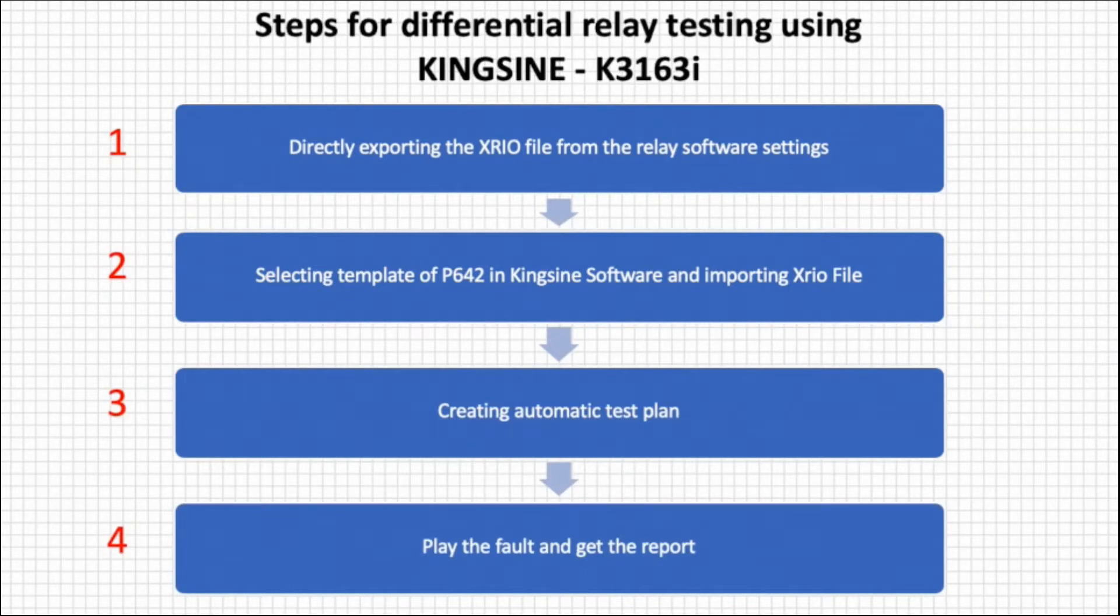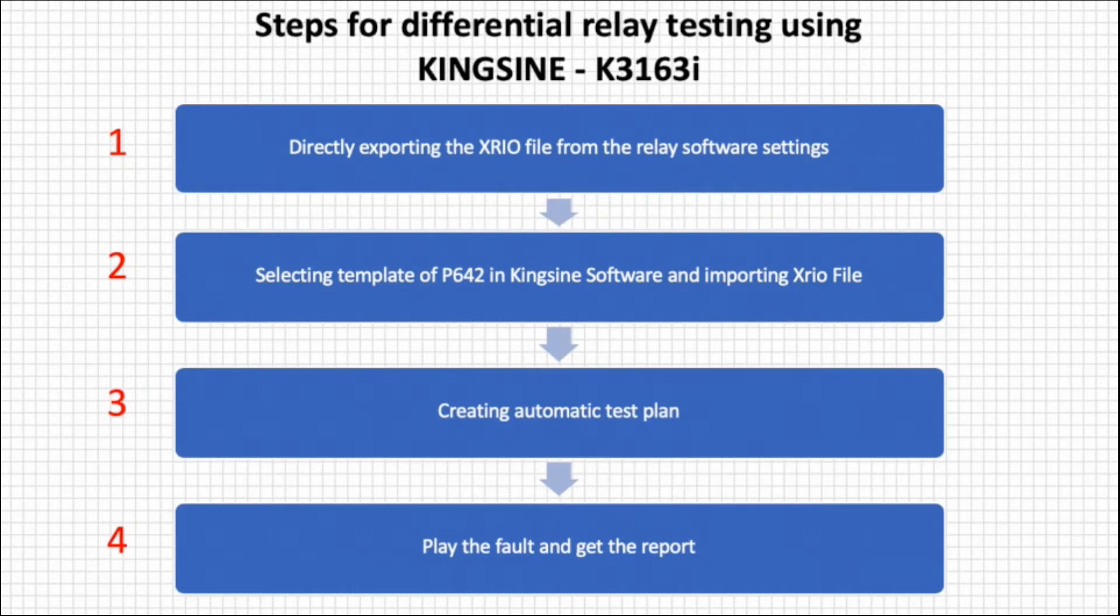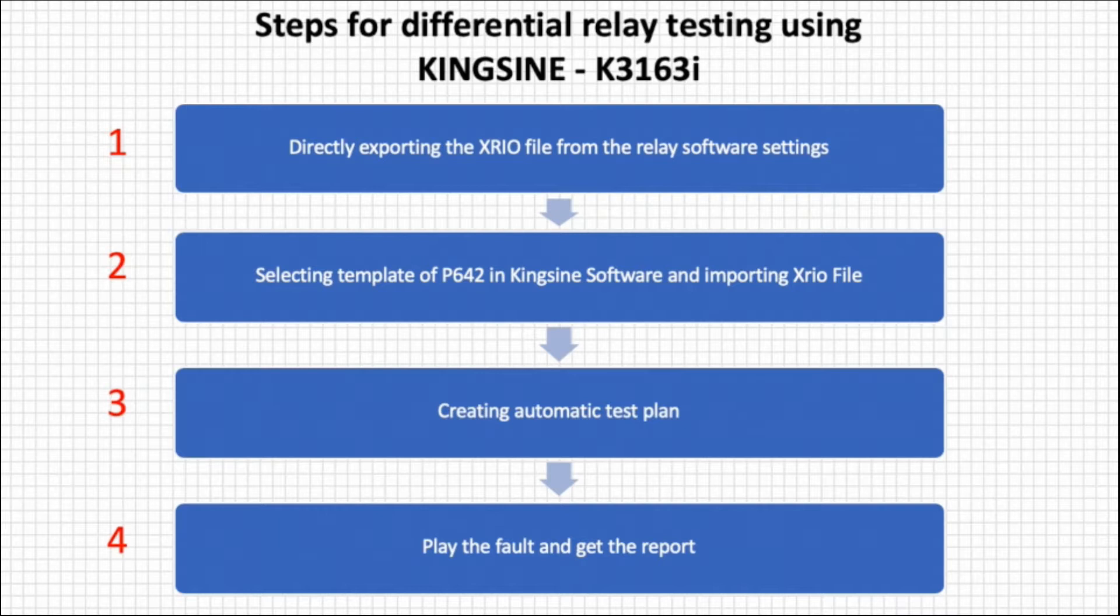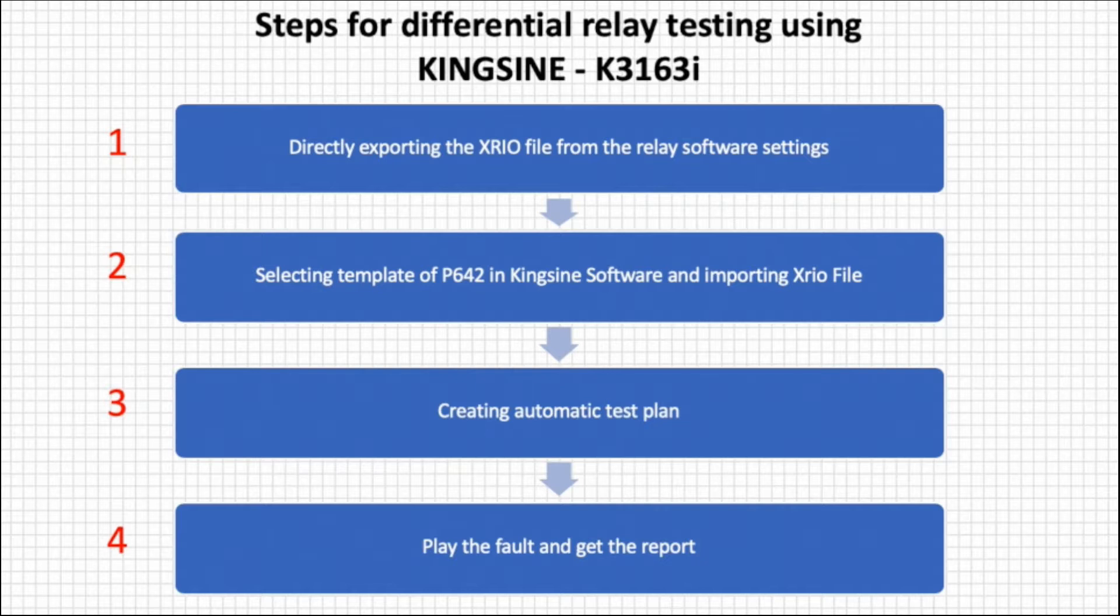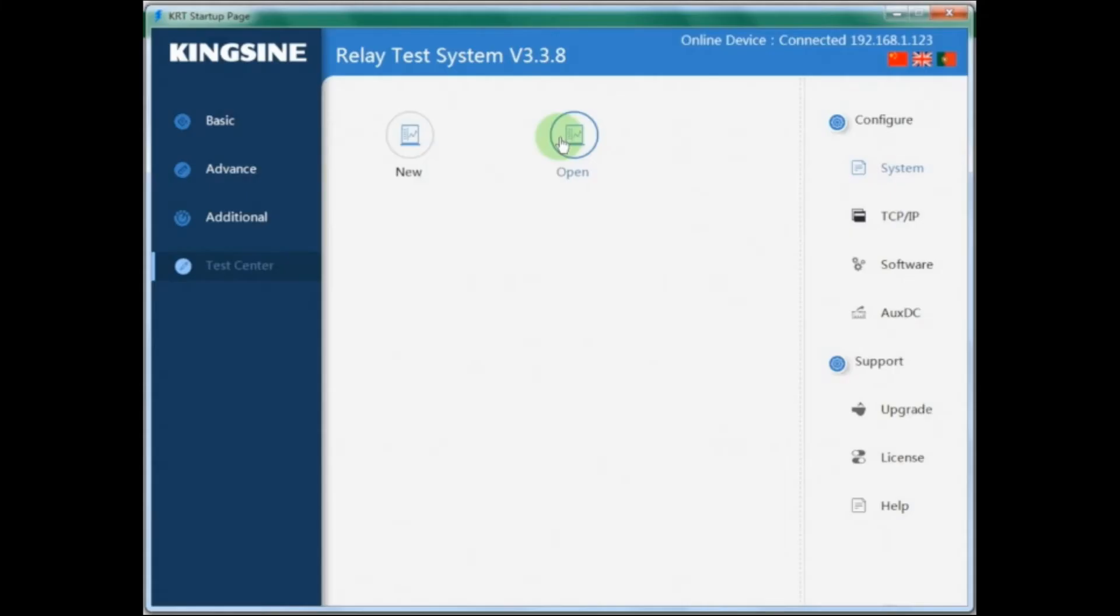First, directly exporting the Xrio file from relay software settings. Second, selecting template of P642 in Kingsine software and importing the Xrio file. Step 3, creating an automatic test plan for bias curve shooting testing, bias curve search, and harmonic restraint. Step 4, playing the fault and getting the report.